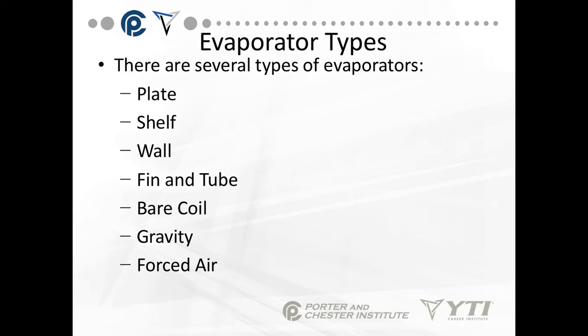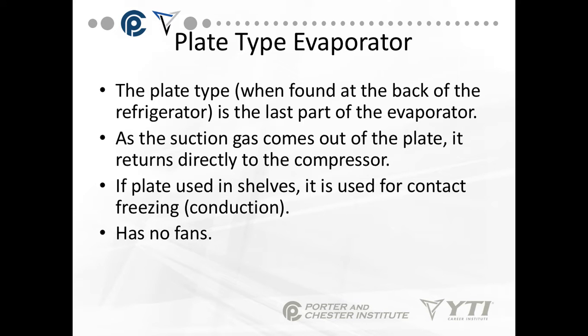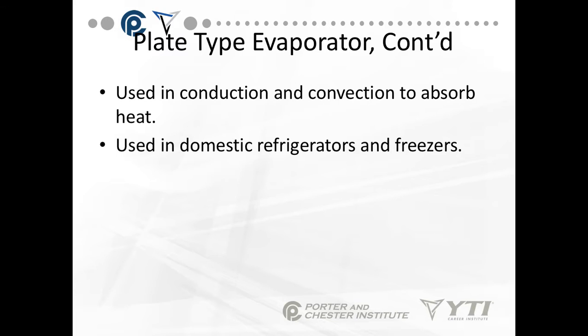There are several evaporator types: plate type, wall shelf, wall evaporator, fin and tube, bare coils, gravity, and forced air. The plate type evaporator is found at the back of a refrigerator — it's a solid plate with tubing or gaps inside. When gas exits the plate it returns directly to the compressor. They're sometimes used on shelves for contact freezing, have no fans, and use conduction and convection to absorb heat, found in domestic refrigerators and freezers like small dorm fridges.